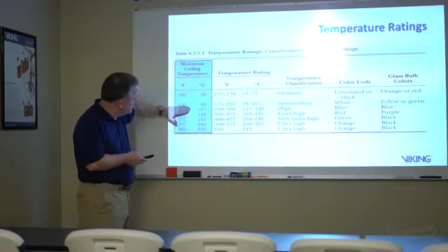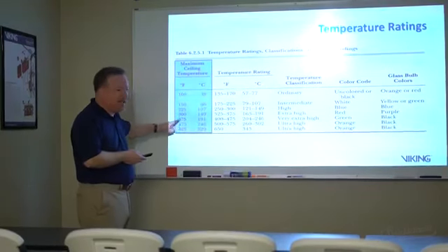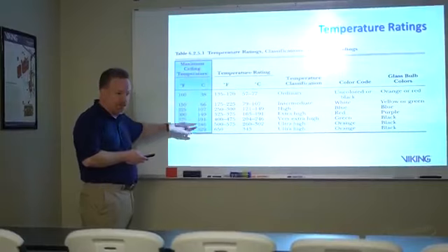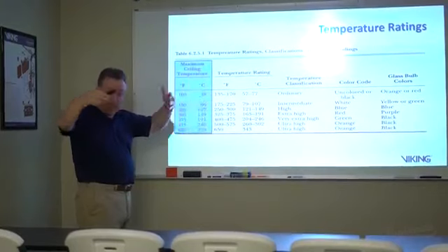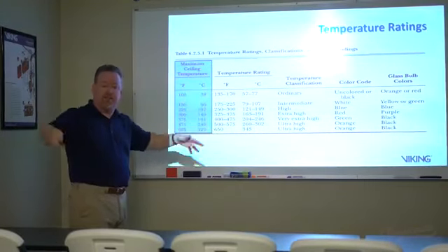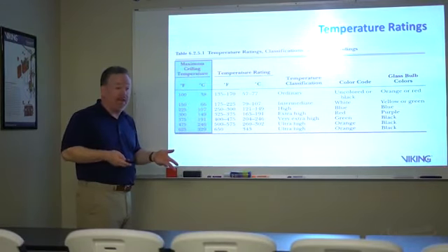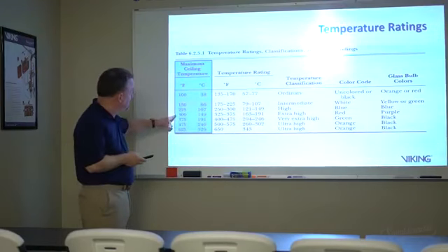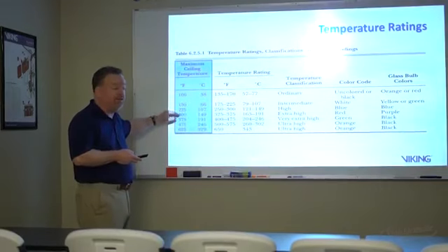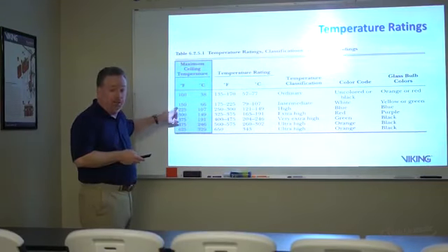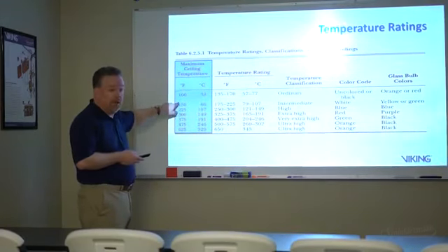And so while it doesn't really play a huge issue down here, you can have certain industrial processes and things like that, right above that space, or heaters in a given area that are pushing out a lot of space heaters and things like that. Again, not something you might run into down here in Florida, but we run into quite a bit, heating the space up. So you may, in localized areas, have temperatures that go up even above 150.